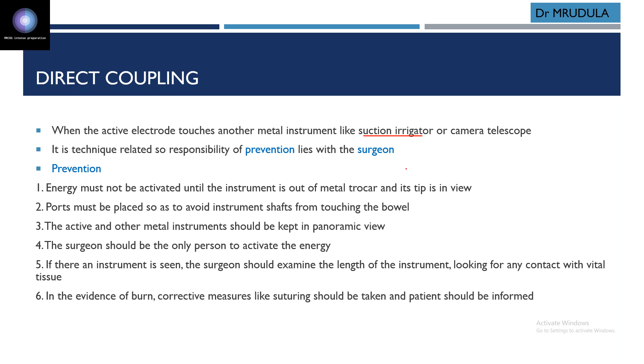Active and other metal instruments should be kept in panoramic view. So whenever you are using a bipolar or monopolar instrument, and in another port you have a suction cannula, both should be in view together. The suction cannula should not be out of view, so that you do not miss direct coupling. The surgeon should be the only person to activate the energy. If an instrument is seen, the surgeon should examine the length of the instrument looking for any contact with vital tissue. In evidence of burn, corrective measures like suturing should be done and the patient should be informed.